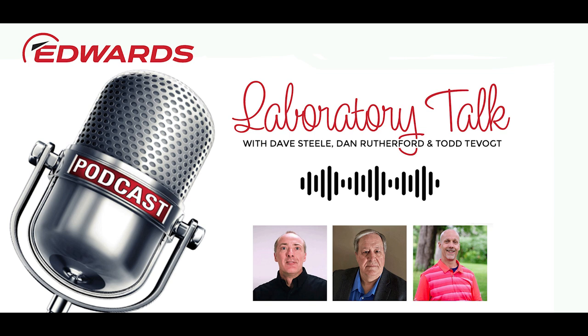A key feature of what an active gauge is and what makes it different from other gauges in use at the time is that all of the sophisticated signal level processing is done in the actual gauge head itself, in an electronics module attached to the gauge head. And so they give a simple 0 to 10 volt DC output that represents the pressure rather than an unprocessed, very low voltage millivolt level signal output.